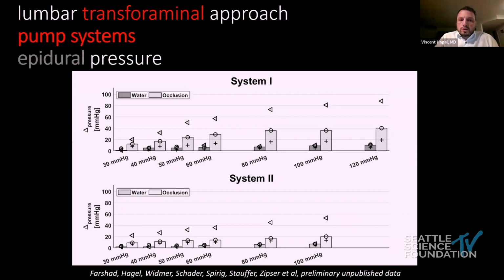If we do not occlude the working channel, then even at high pressure settings, all the way to 120 millimeter mercury for system one, it does not significantly increase the epidural pressure. If we occlude the working channel, then of course, the higher we set the pressure, the more we do increase the epidural pressure. And now we do have values obviously way above 20 millimeter mercury, but still it behaves similar to the gravity system. The high epidural pressures do not reflect into intradural pressures, so the intradural pressures are still within the physiological range.